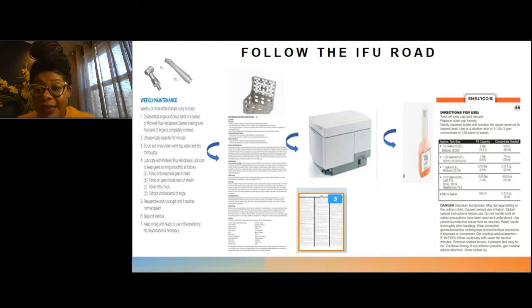Well, that small case has its own IFU. Yes, the product manufacturer of the case that you place it in has its own IFU, and that IFU tells you, hey, if you're going to reprocess anything in our little case, you need to reprocess it for this amount of time. If you're going to place it inside of an ultrasonic, it needs to go in that time. But then the IFU for the contra angle head told you it needs to go in for 10 minutes. What do you do when the IFU then says, hey, if you put it in this little container, it needs to go in for that time as well?